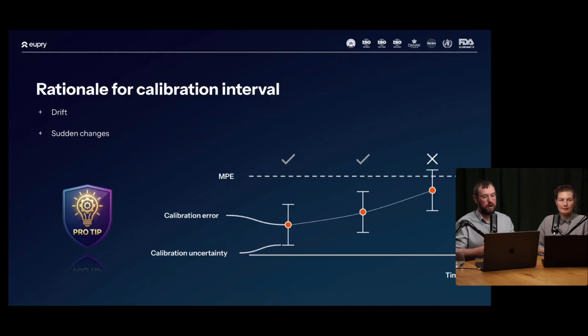I know that in a lot of forums and a lot of discussions, PT100 sensors are seen as a homogeneous mass of sensors, but they are very, very different. Typical drift would be something like 0.05 degrees per year for a typical sensor to be used in a fridge or in a control room temperature, just to give you some idea of the scale of things. Our reference equipment drifts 0.00 or 0.01 degrees per year. It's a very, very stable piece of equipment. But then again, it really depends on how you're using it.